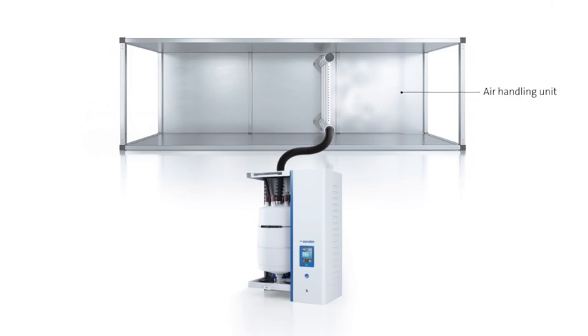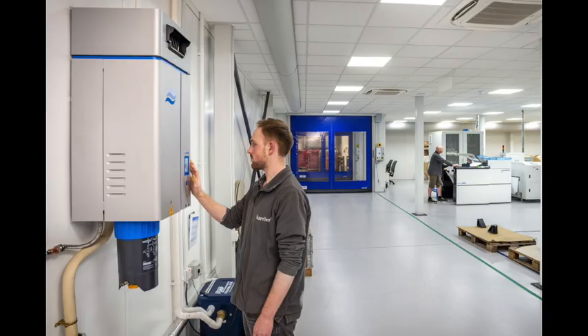So are air handling units not able to control humidity to start with? No, not always. A lot of AHUs are fitted with a space for a humidifier, should one be needed, so they can be retrofitted if the need arises. However, sometimes even with an AHU in a building, there can be times when it's better to fit the humidifier locally. For instance, if humidity control is only needed in one area of a large building, it can be cheaper to use a single small direct room humidifier.